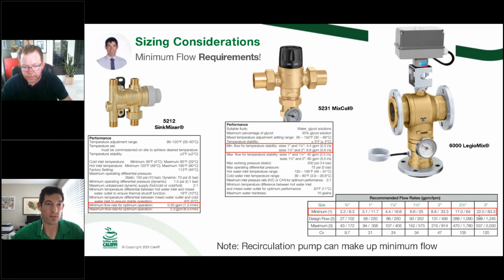So going back to the far left there, the sink mixer, that's a point of use mixing valve that's meant to go under a sink, and it goes all the way down to 0.35 GPM. So that's going to be the appropriate valve for just a single shave situation, or a normal up to 2.3 GPM under a sink. That's the valve that you want for that particular use case. If you're looking at a hospital or a city block, then maybe you go with the big 3-inch flange Legio mix on the right there. But one of the things that you should look for with the mixing valve is what is published in the technical brochure for minimum flow rate, to make sure that you're in the ballpark there. And then you kind of go up in size across from left to right.